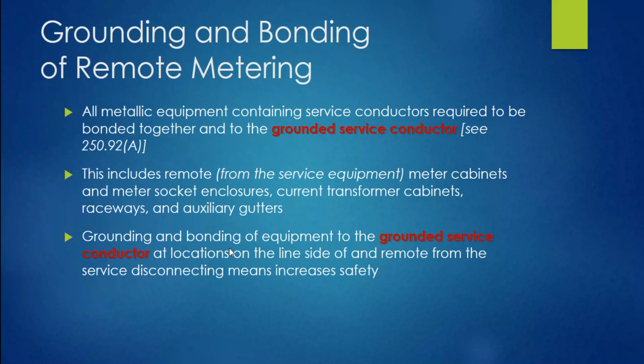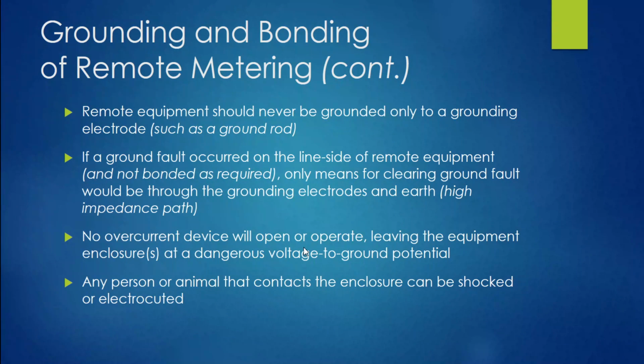Now, the grounding and bonding of equipment onto the grounded service conductor at locations on the line side of the service disconnection means increased safety. It's no different. We were talking about that earlier when it came to the line side and all those raceways, tying together increases the safety. The same rule applies here. Now, remote equipment should never be grounded only to a grounding electrode, such as a ground rod. Okay? It needs to be connected to the grounded conductor.